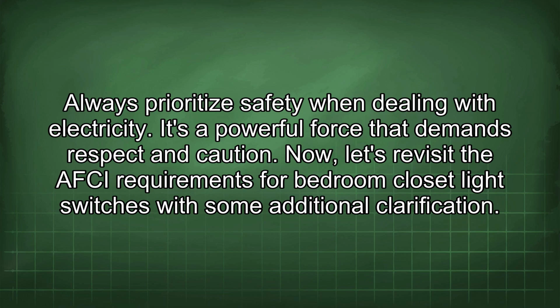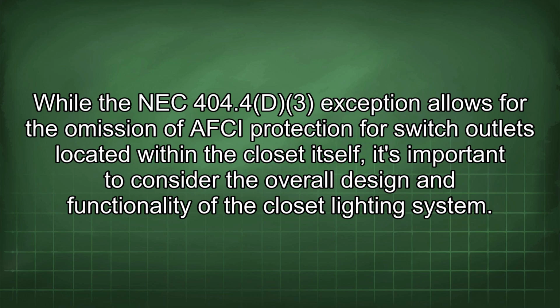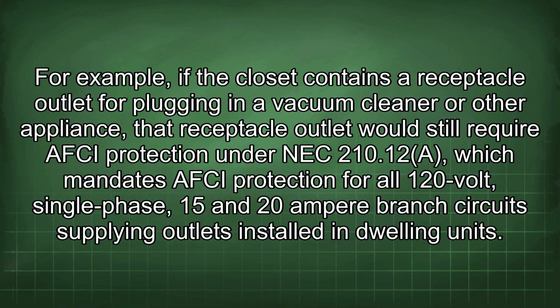Now, let's revisit the AFCI requirements for bedroom closet light switches with some additional clarification. While the NEC 404.4D3 exception allows for the omission of AFCI protection for switch outlets located within the closet itself, it's important to consider the overall design and functionality of the closet lighting system. For example, if the closet contains a receptacle outlet for plugging in a vacuum cleaner or other appliance, that receptacle outlet will still require AFCI protection under NEC 210.12(A), which mandates AFCI protection for all 120-volt, single-phase, 15 and 20 ampere branch circuits supplying outlets installed in dwelling units.